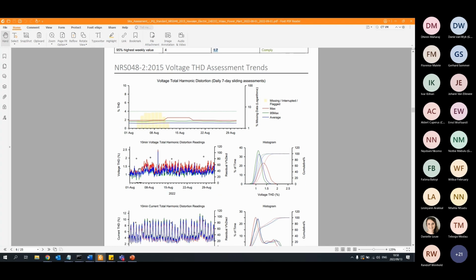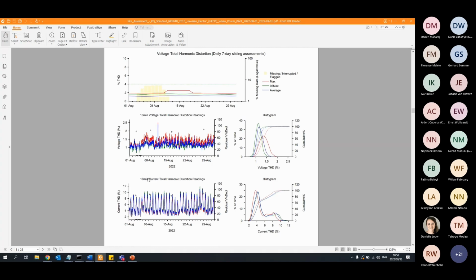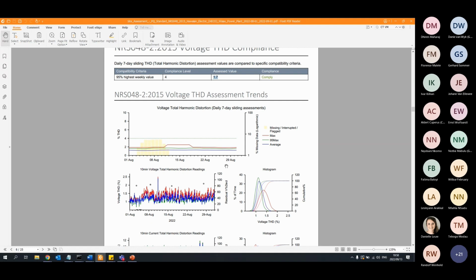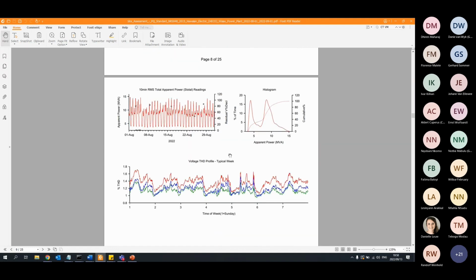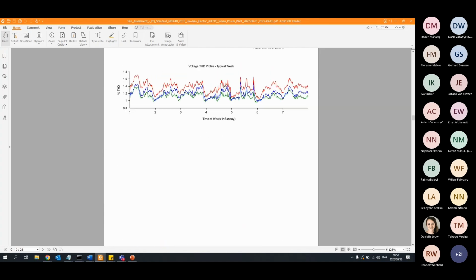You can see how your THD, the 10-minute values, changes over time over this month period. You can see there was an increase in the THD at that point. And then you can also compare that with your current THD as well. But the voltage THD is used for the assessment. Here we can see how it changes over time, or a typical week.